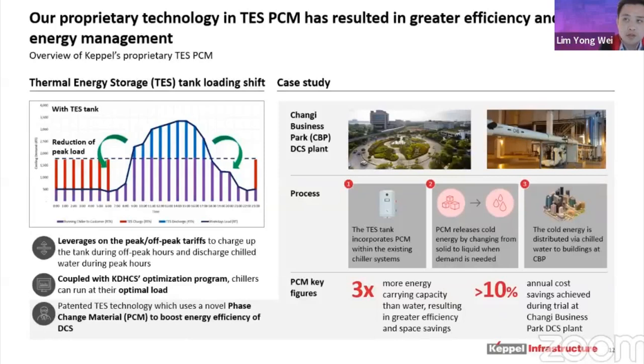As you can see, thermal energy storage helps reduce the peak load of an entire development, shaving a peak load of about 3,500 R-ton down to less than 2,000 R-ton. This translates to leveraging the peak and off-peak tariff: we charge the tank during off-peak hours and discharge chilled water during peak hours.